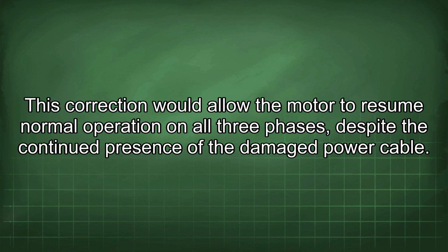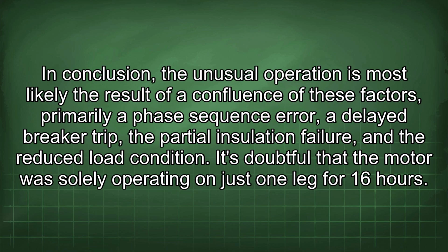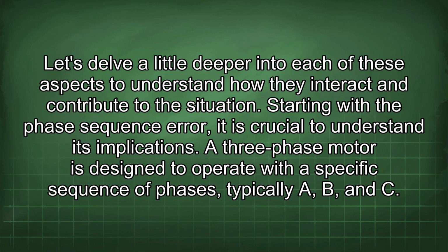damaged power cable. In conclusion, the unusual operation is most likely the result of a confluence of these factors, primarily a phase sequence error, a delayed breaker trip, the partial insulation failure, and the reduced load condition. It's doubtful that the motor was solely operating on just one leg for 16 hours. Let's delve a little deeper into each of these aspects to understand how they interact and contribute to the situation.